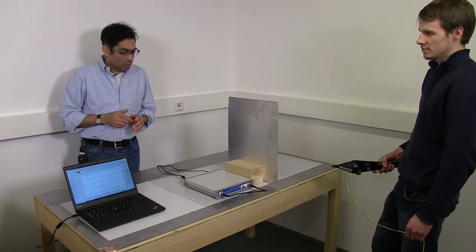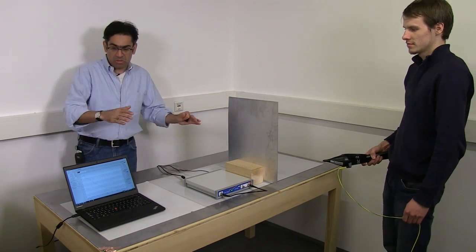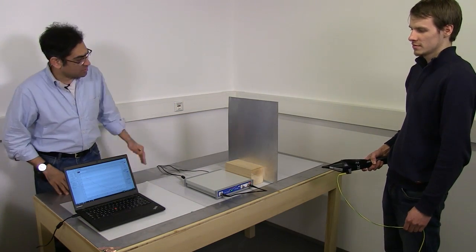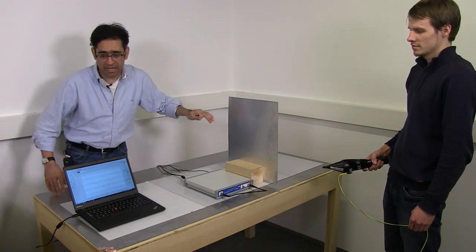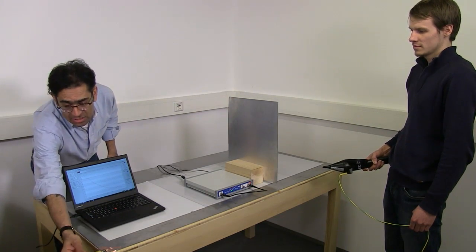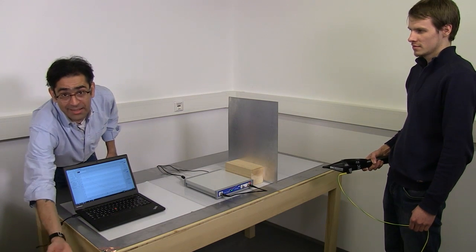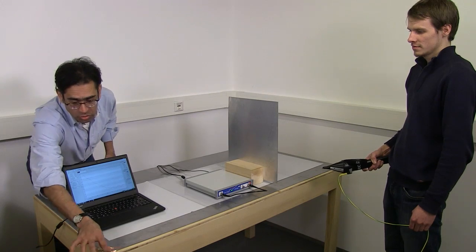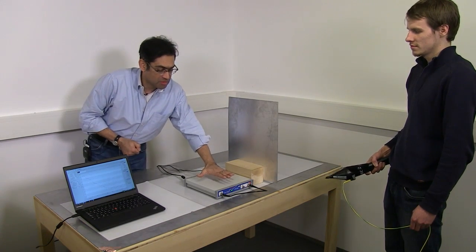So for an ESD pre-compliance test, this is a typical test setup. You have got a vertical coupling plane, you have got a horizontal coupling plane. This part is actually tied via about 1M to a metal plane on the floor to give you good coupling down to the floor. And the equipment on test will sit over here.